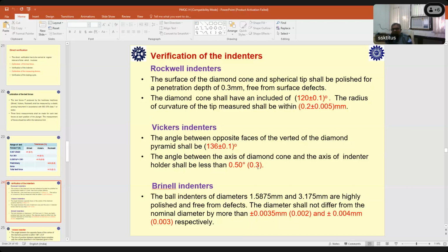There are not many suppliers even all over the world for the indenter for the part 3 machine. Even after making the indenter, if it is not fulfilling this stringent requirement, then it becomes a kind of waste. So you make a diamond indenter. If you make say 100 indenters, maybe one or two will qualify for the part 3 indenters. Part 3 means the machine which is used as a calibration machine for the standard hardness block. The indenter is a very critical component.